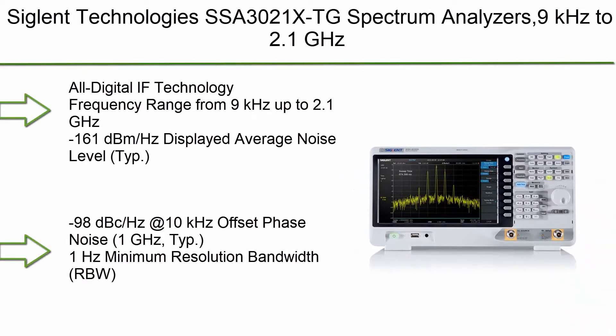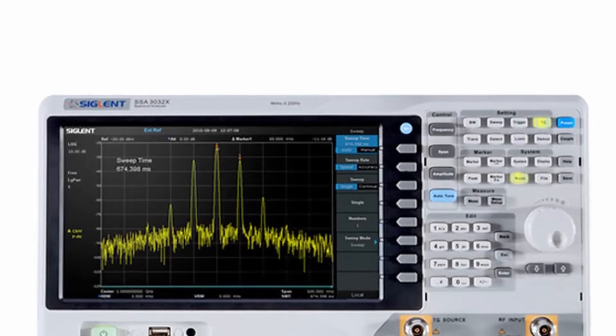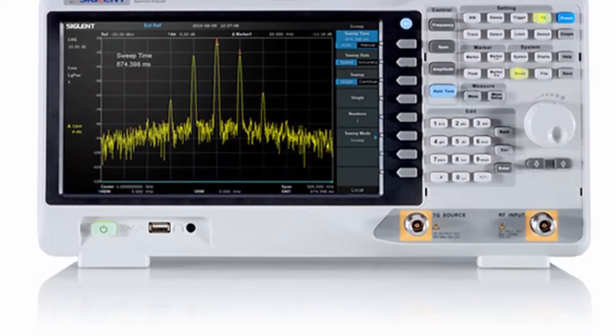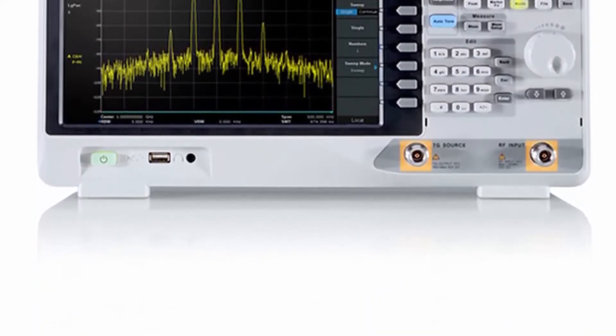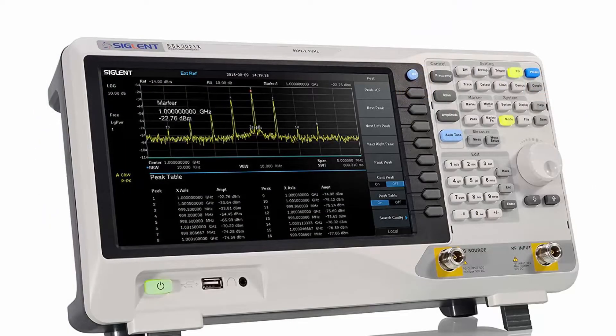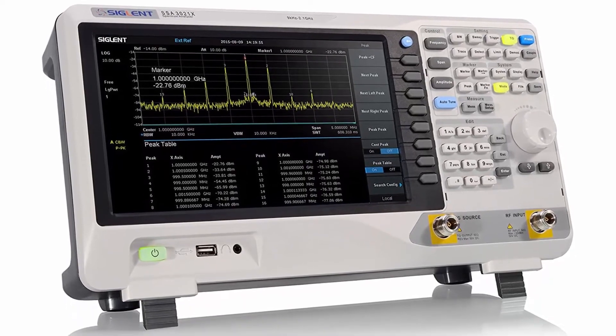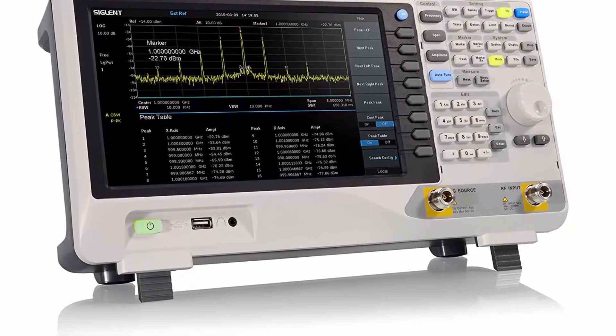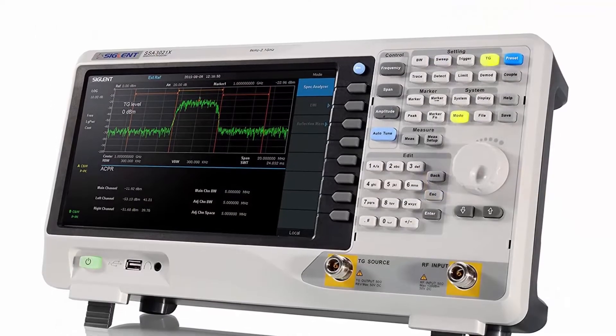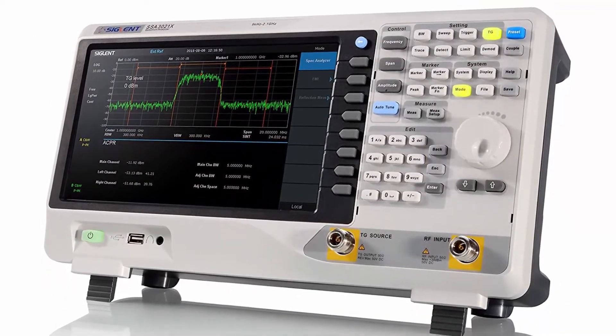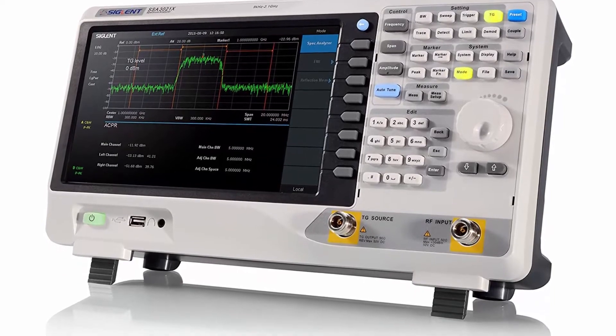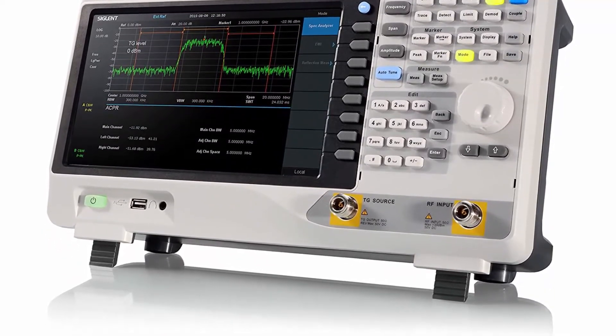Top 9: Siglent Technologies SSA-3021XTG Spectrum Analyzer — 9 kHz to 2.1 GHz with free tracking generator. All digital IF technology. Frequency range from 9 kHz up to 2.1 GHz. -161 dBm/Hz displayed average noise level typical. -98 dBc/Hz at 10 kHz offset phase noise at 1 GHz typical. 1 Hz minimum resolution bandwidth (RBW).